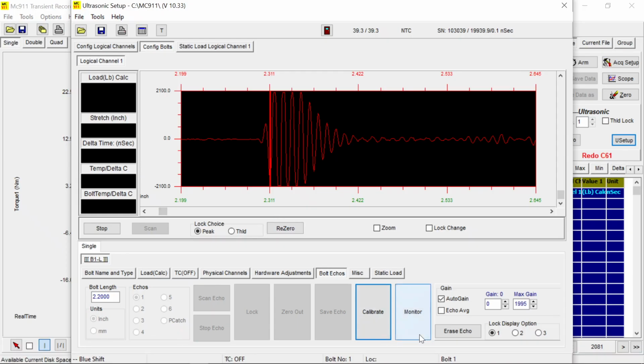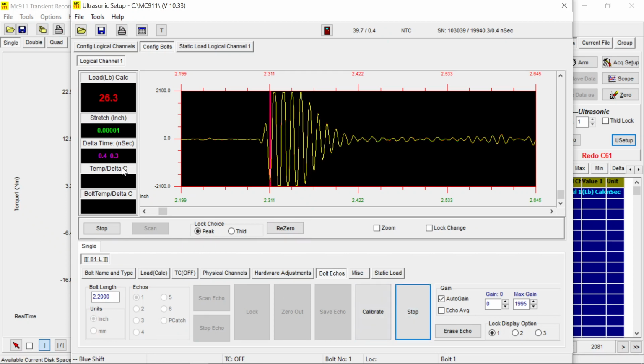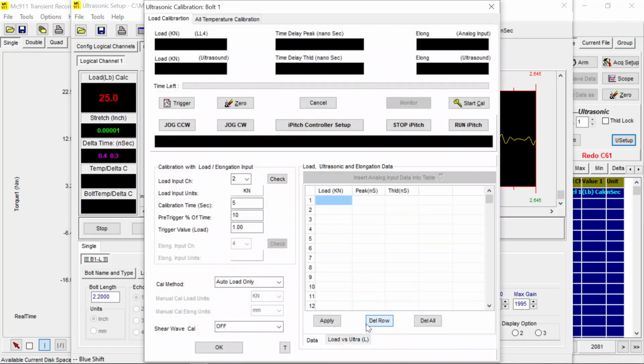Okay. Now, as you monitor it, this is the load that's sitting in there. There is no load, and just in calibration mode, we want to calibrate this. Click on calibrate. Since we have iPitch, these other buttons show up below the standard buttons. To start with, we can click on Start Cal. We can see that the ultrasonic signal is alive. We can zero it, and our load also shows 0 kilonewton. Let me cancel this and explain something.